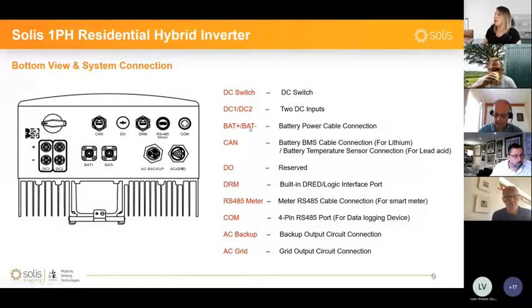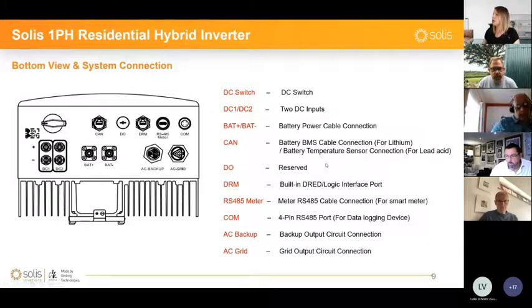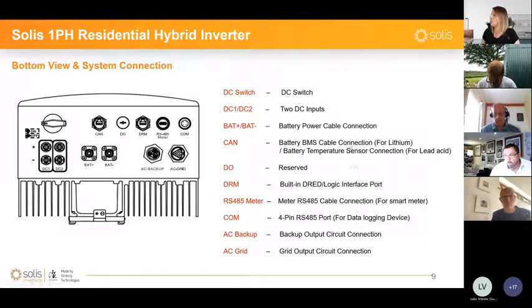Additionally, we have the battery connections, plus and minus, where you would normally connect the power cables. The CAN communication port, which is actually an RJ45 plug, is used for connection to the battery control management systems, the BMS, as it is called. And if we're talking about a lead acid, there you would connect the battery temperature sensor.